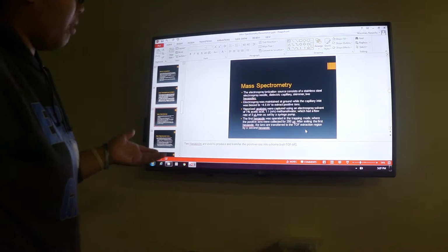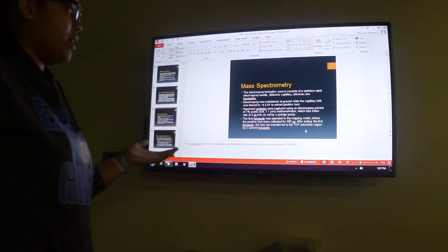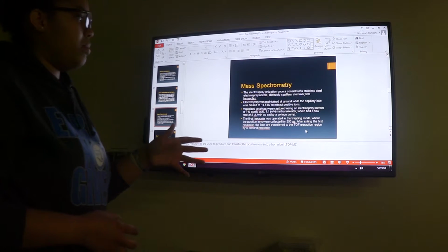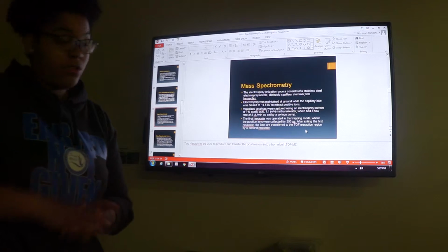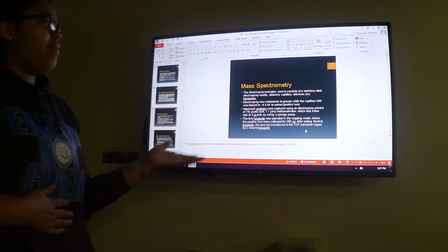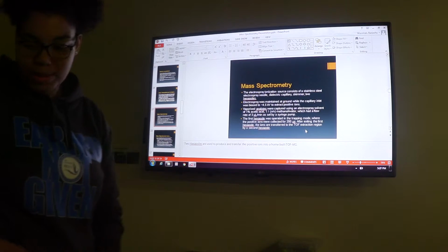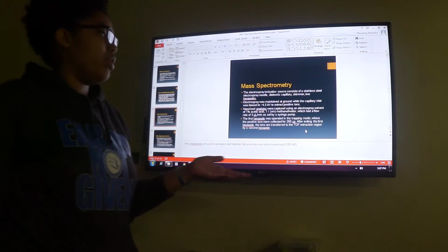So the mass spectrometry involved: the ESI consisted of a stainless steel electrospray needle, a dielectric capillary, and a skimmer, as well as 2 hexapoles. The electrospray was maintained at ground, with the capillary inlet biased to about negative 4.5 kilovolts to extract the positive ions from the sample. The vaporized analytes were captured using the electrospray solvent, which was about 1% acetic acid in a 1-to-1 ratio of methanol and water, with a flow rate of about 3 microliters per minute set by the syringe pump.